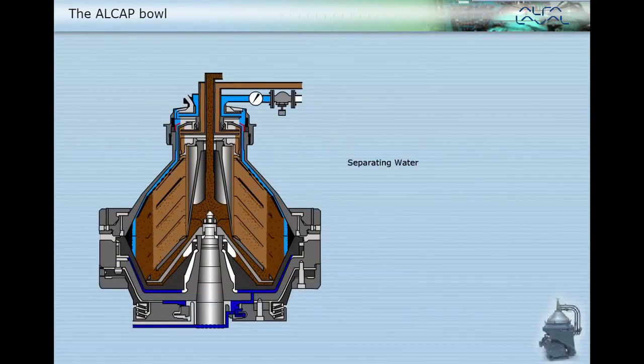Some water separates from the oil. As the drain valve is normally closed, the water cannot immediately pass that way. As the water is separated, the interface will move inwards until it reaches the disc stack.